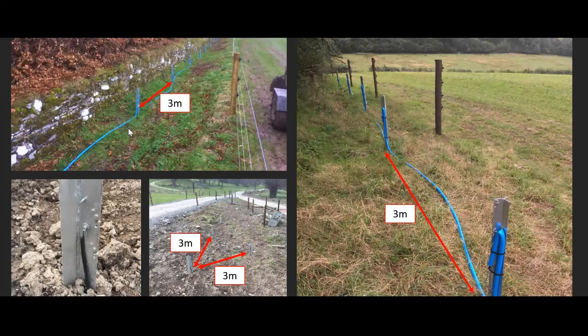The posts themselves are 3 meters apart, and then they're connected in series by 2.5 millimeter underground cable. You can see in a couple of the options that cable has been run on the surface and sheathed in water pipe to protect it from animals, from livestock, and from traffic. One example there has actually been buried under the ground. You're probably just using a spade to dig a shallow trench and bury it 6 inches underground, again to keep it safe. So all those posts are linked up, and that's the key component of this effective earthing system.